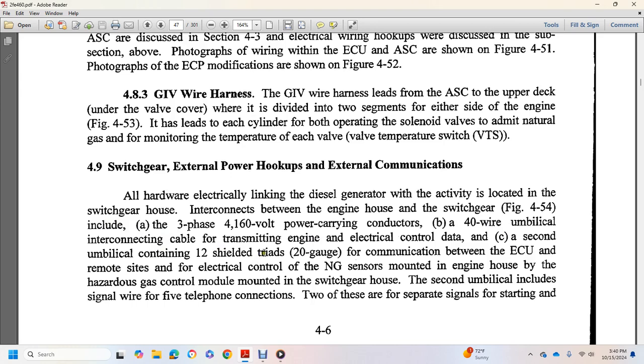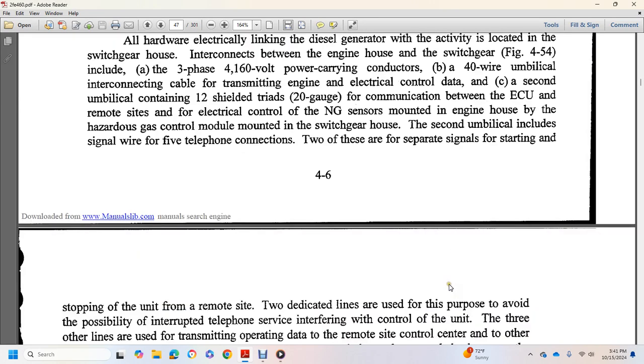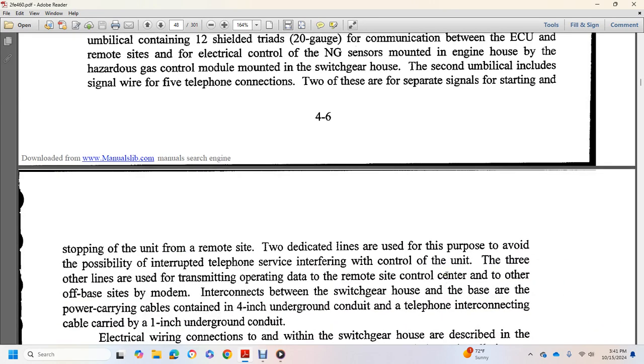The umbilical contains 12 shielded triads at 20 gauge for communication between the engine control unit and the remote site, with electronic control of the natural gas sensors mounted within the engine housing by the hazard gas control module mounted in the switchgear housing. A second umbilical includes signal wire and 5 telephone connections. 2 of these are separate signals for stopping units from the remote site, 2 dedicated lines with the purpose of avoiding the possibility of interrupted telephone service interfering with the control of the unit. 3 of the other lines transmit operating data to the remote site control center.